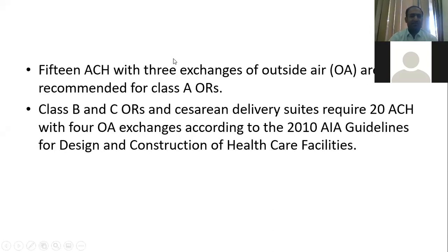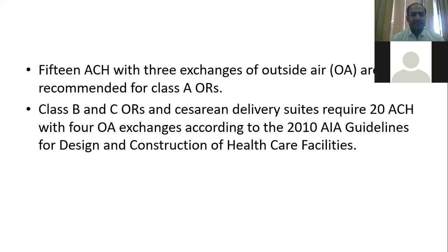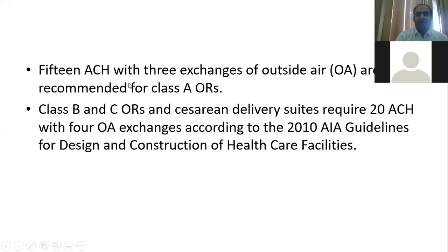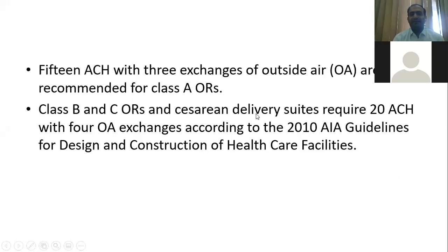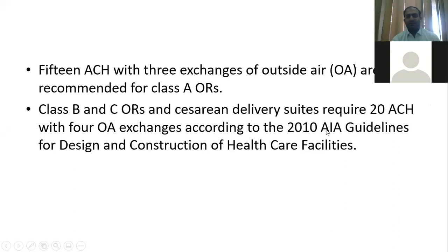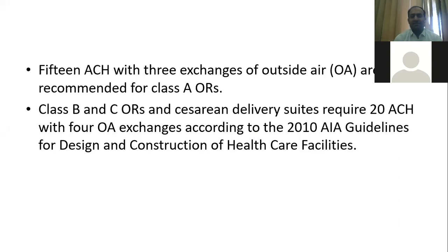For a Class A operating room with a 150 square foot floor area, at least 15 air changes per hour (ACH) are required, with three exchanges of outside air. According to the 2010 2010 AIA (American Institute of Architects) Guidelines, Class B and C operating rooms also have specific ACH requirements.